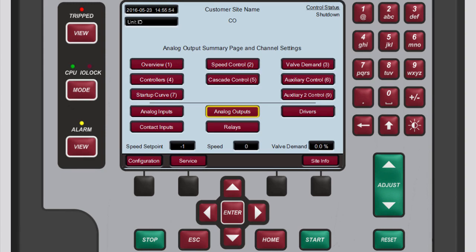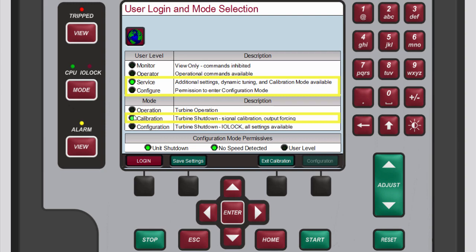You can also use the 505 controller to force analog output values. This can be helpful in testing and troubleshooting. To do this, log into either the service or configure user level and put the controller into calibration mode. If you aren't sure how to do these things, refer to the changing user levels and changing modes and languages tutorials.